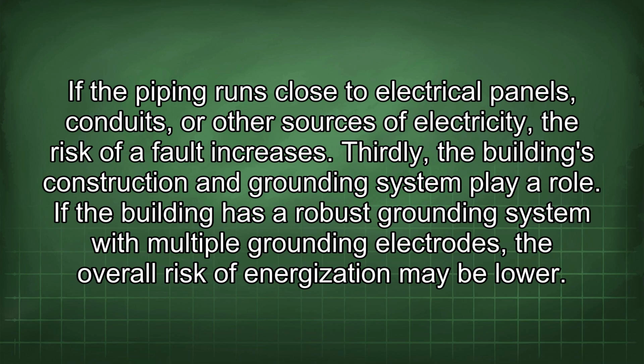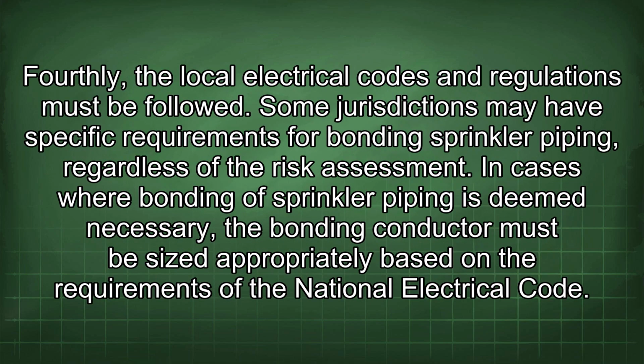Thirdly, the building's construction and grounding system play a role. If the building has a robust grounding system with multiple grounding electrodes, the overall risk of energization may be lower. Fourthly, the local electrical codes and regulations must be followed. Some jurisdictions may have specific requirements for bonding sprinkler piping, regardless of the risk assessment. In cases where bonding of sprinkler piping is deemed necessary, the bonding conductor must be sized appropriately based on the requirements of the National Electrical Code.